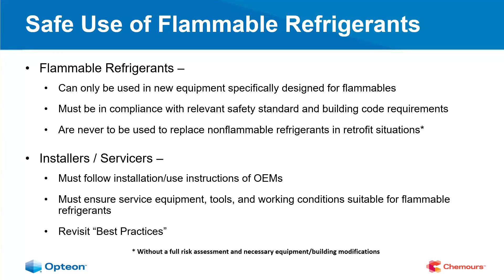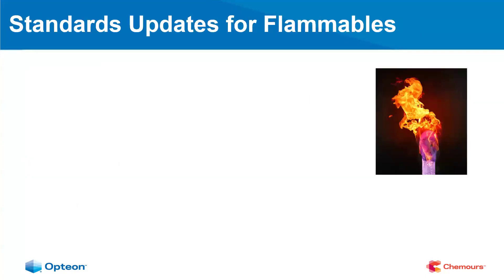It's also time to reinvigorate our commitment to best practices: full recovery of refrigerant from a system before opening it to the atmosphere, deep evacuation before putting the system back in service, and using a nitrogen purge while brazing or soldering. These have always been best practices, but now with the move to flammable refrigerants they are a fundamental requirement. Re-embracing those best practices is key to a successful transition.